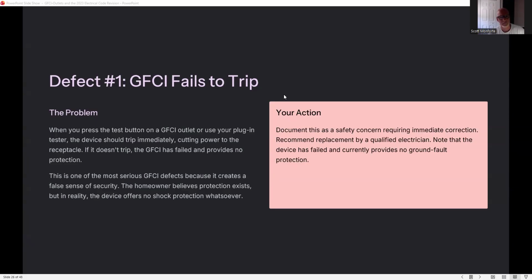Document this as a safety concern requiring immediate correction. Recommend replacement by a qualified electrician. Note that the device has failed and currently provides no ground fault circuit interrupter. This is the biggest one that you have.